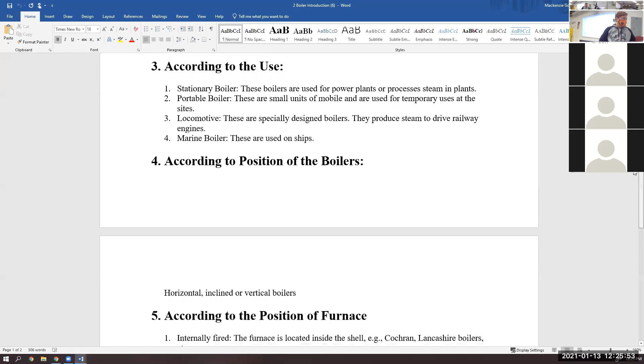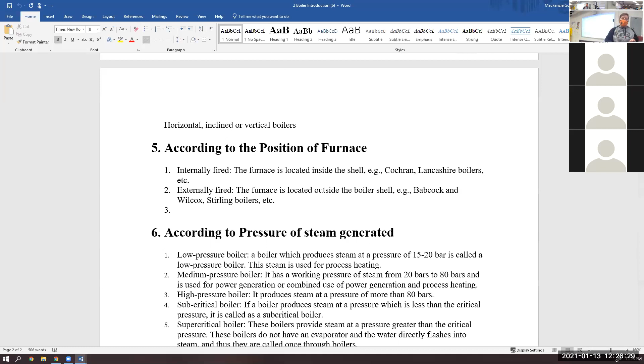You can arrange the direction of the tubes, whether fire tube or water tube, to fit in a certain space, or to take advantage of certain climate factors that make harnessing natural circulation a little easier. If it's less humid, natural circulation is a bit more forceful, so you could take advantage of it in a horizontal arrangement. Sometimes you need that water to stay in the flue gases longer, so you make loops and go horizontal. It just depends on the design of the plant.